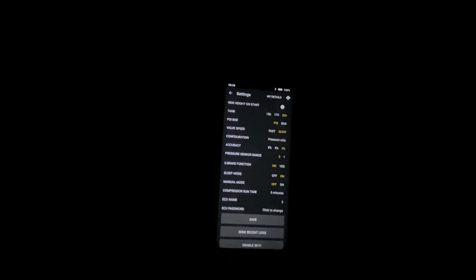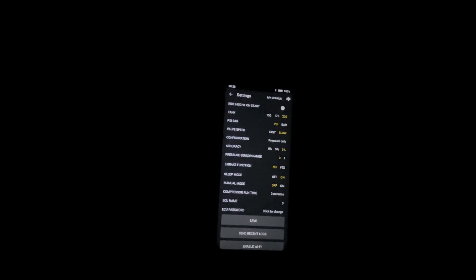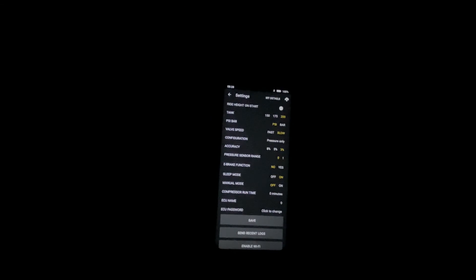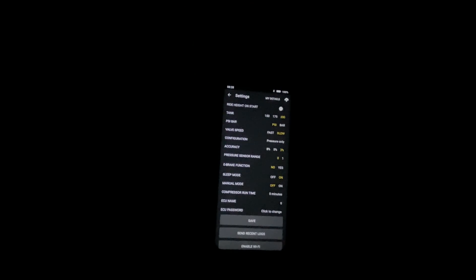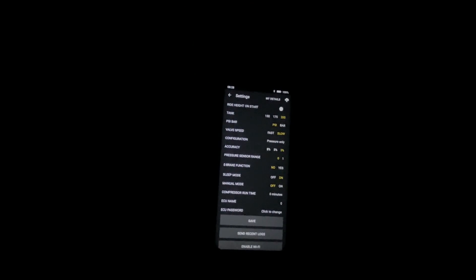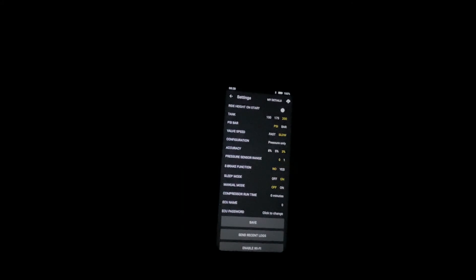The pressure sensor range is our two types of pressure sensors. The zero is our half volt to four and a half volt, and the one is our zero to five volt sensors. All the systems at the moment are shipped with the half volt to four and a half volt, so that is set as default.